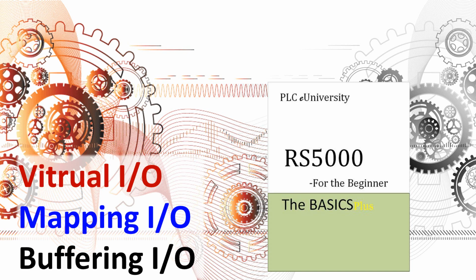In other words, activate each module one at a time, collect the data into input words, then execute the program, and then stop executing the program, go and take all of the output images and transfer them out to cards on the backplane. And that's why they call it an active backplane, because the processor has to activate through the control bus each module one at a time, either collect information or transfer information out.